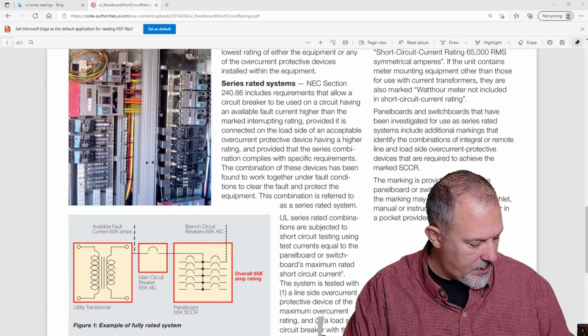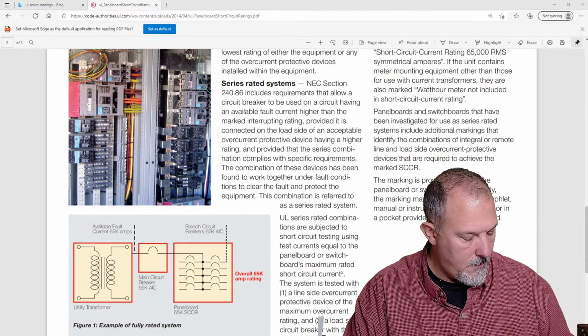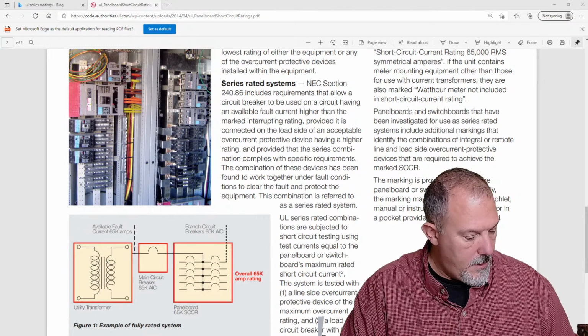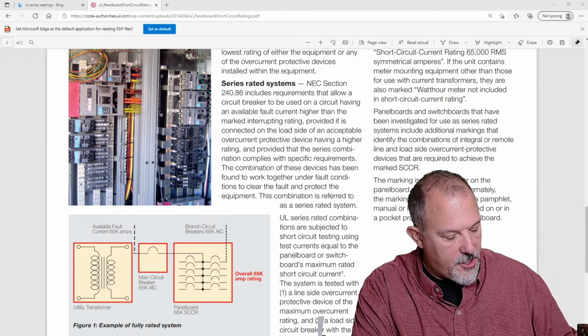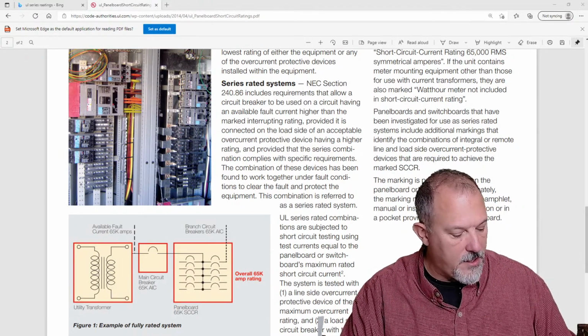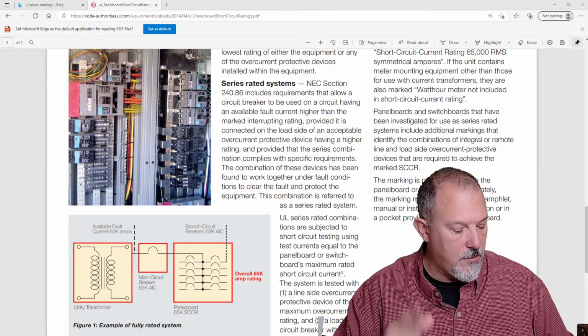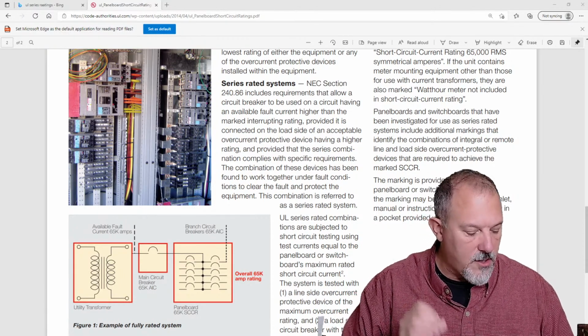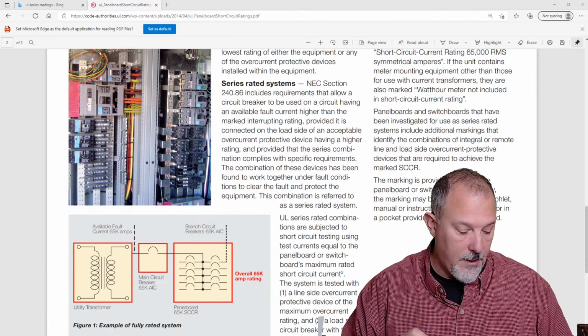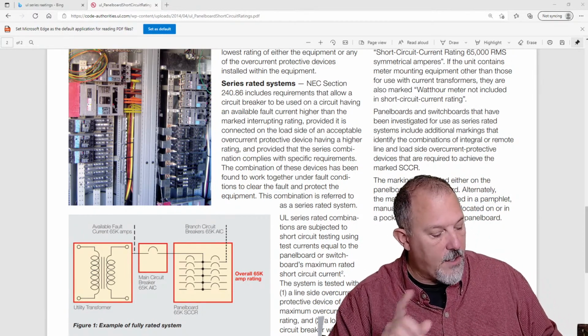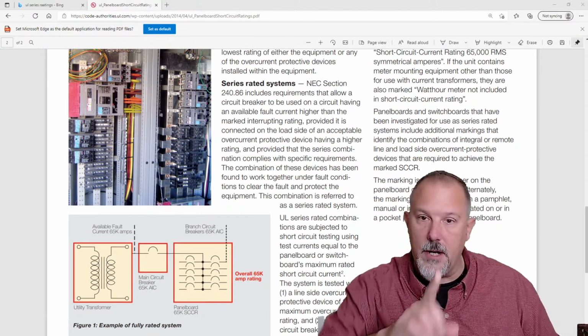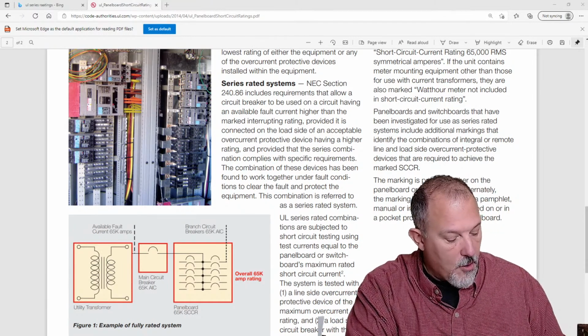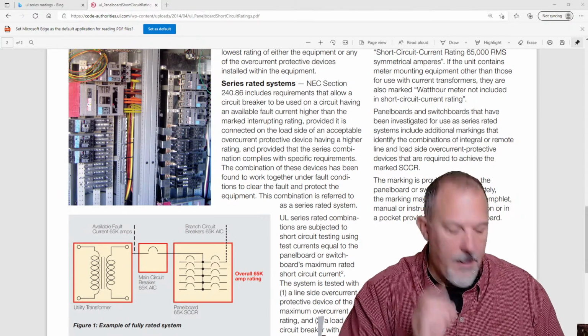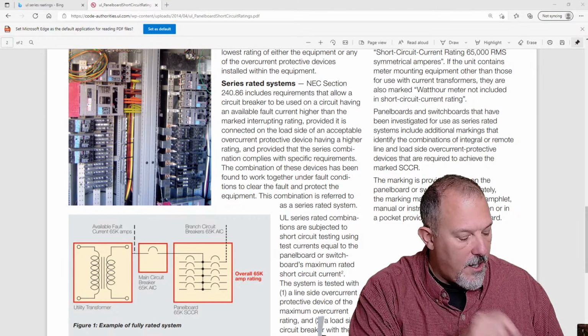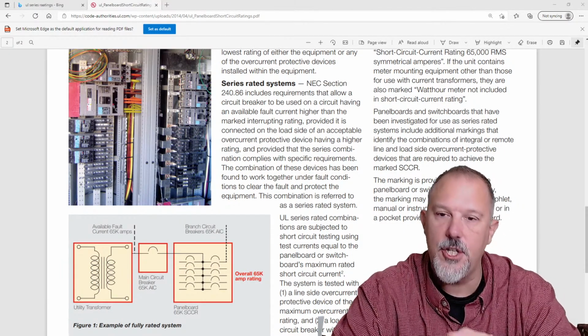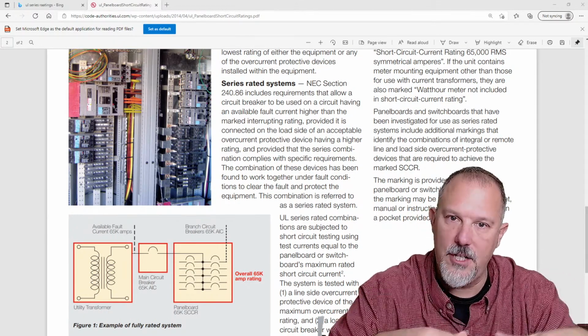240.86 tells us for an engineered series rating, okay, the series rated combination devices shall be selected by a licensed professional engineer engaged primarily in the design and maintenance of electrical installations. The selection shall be documented and stamped by the professional engineer. The documentation shall be available to those authorized to design, install, inspect, maintain, and operate the system. The series combination rating, including identification of the upstream device, shall be field marked. For calculated applications, the engineer shall ensure that the downstream circuit breakers, which is what you have in your panel board, that are part of the series combination remain passive during the interruption period of the line side fully rated current limiting device. And there's the text. I'll tell you, because of that language, it makes it almost impossible for you to engineer series ratings.